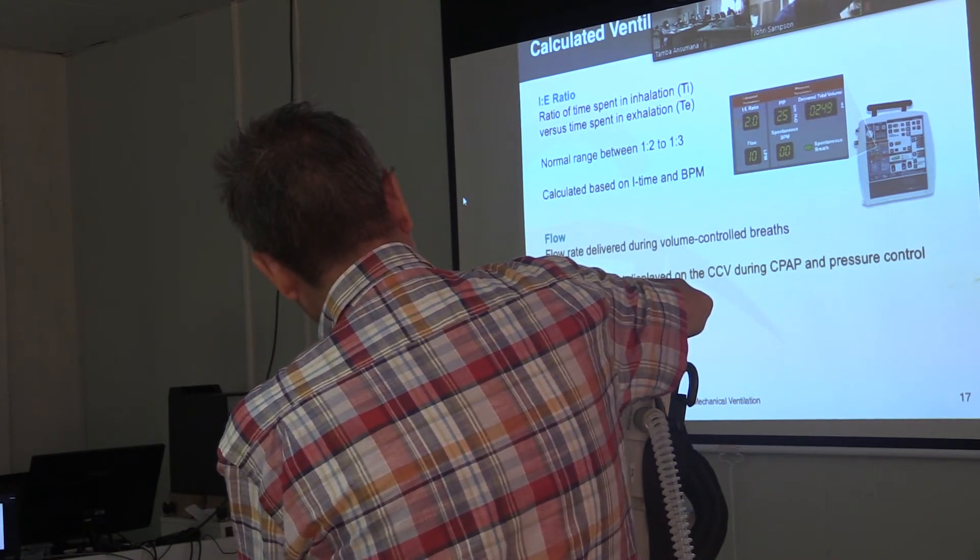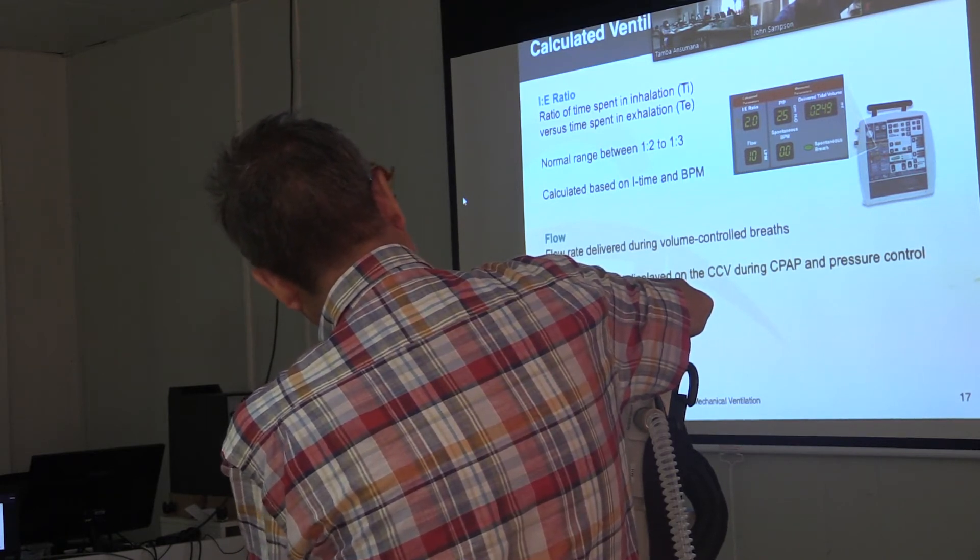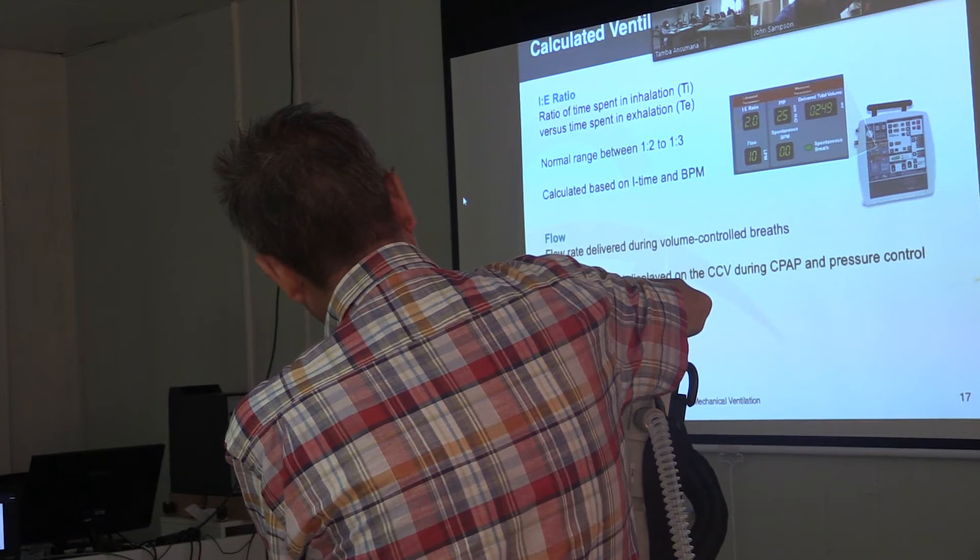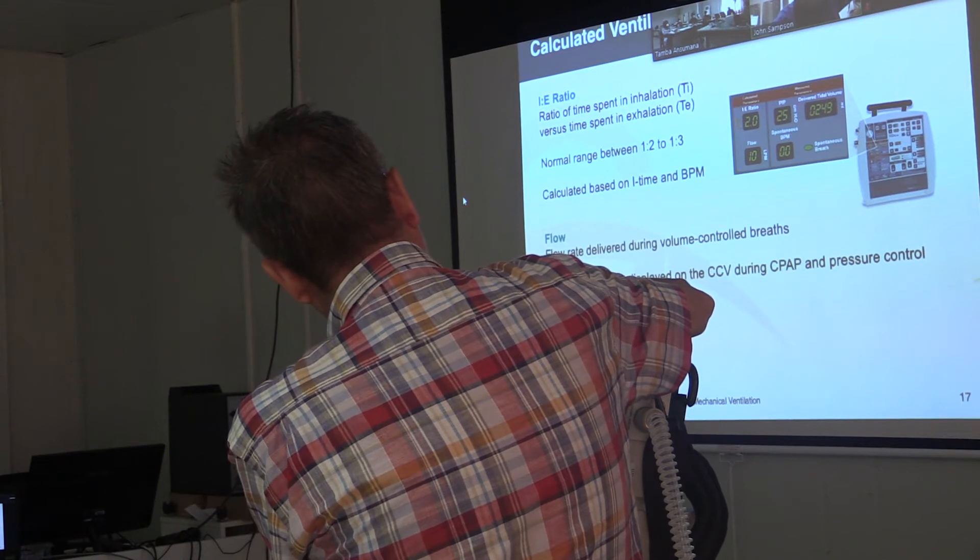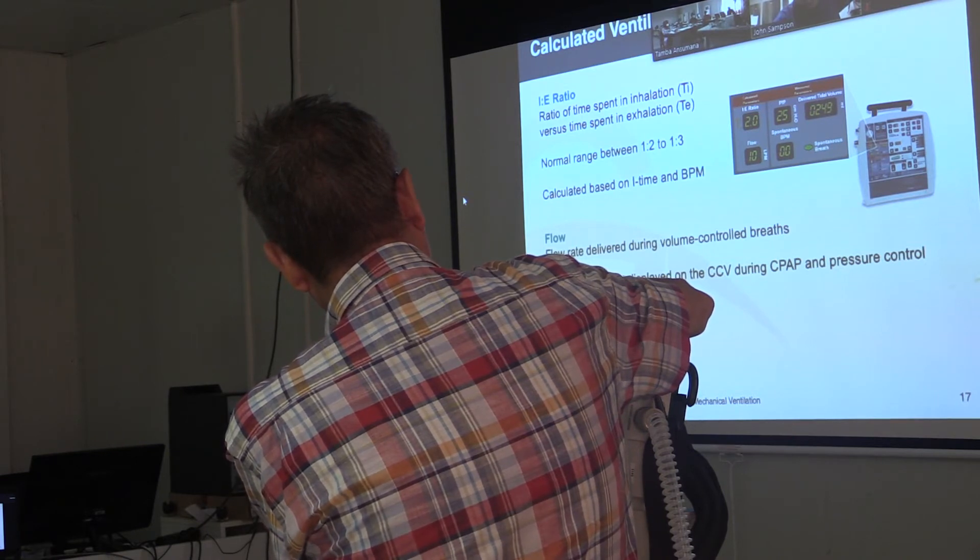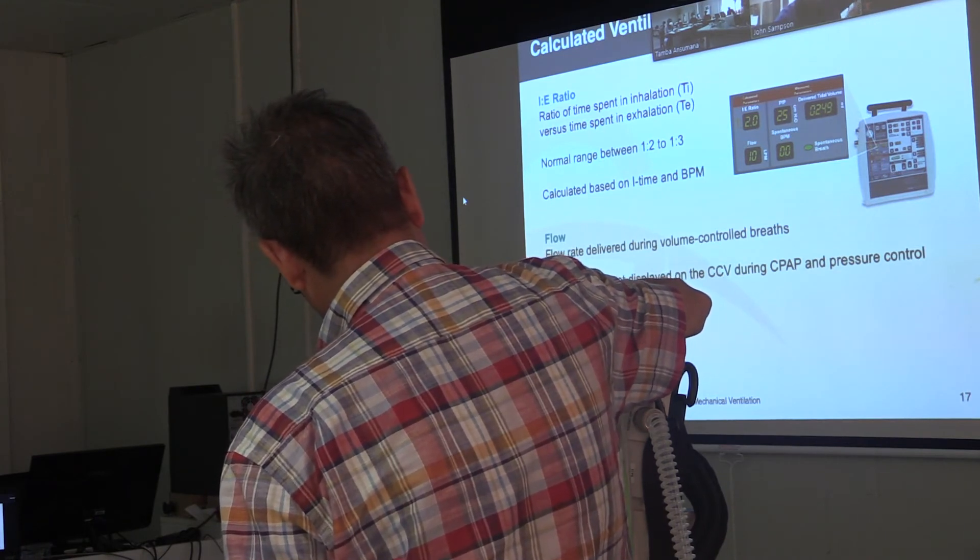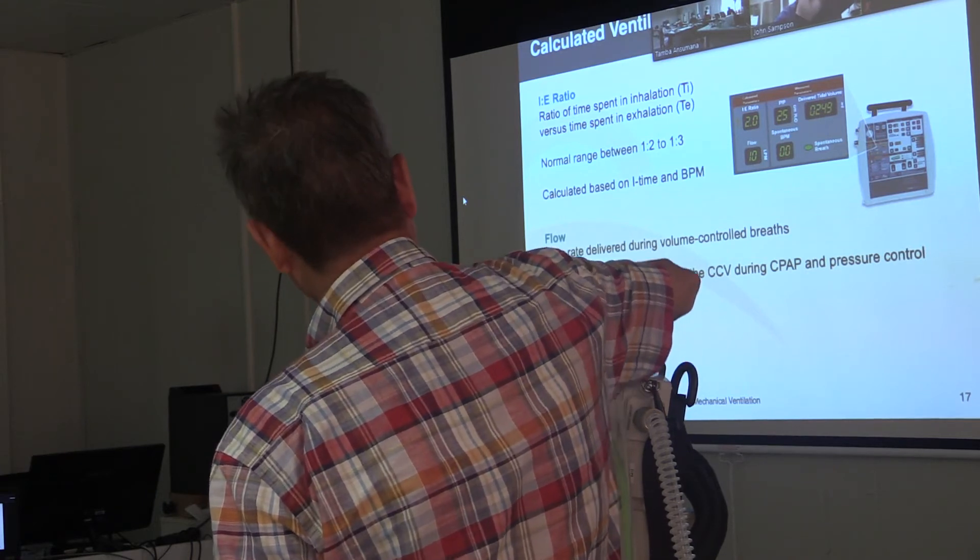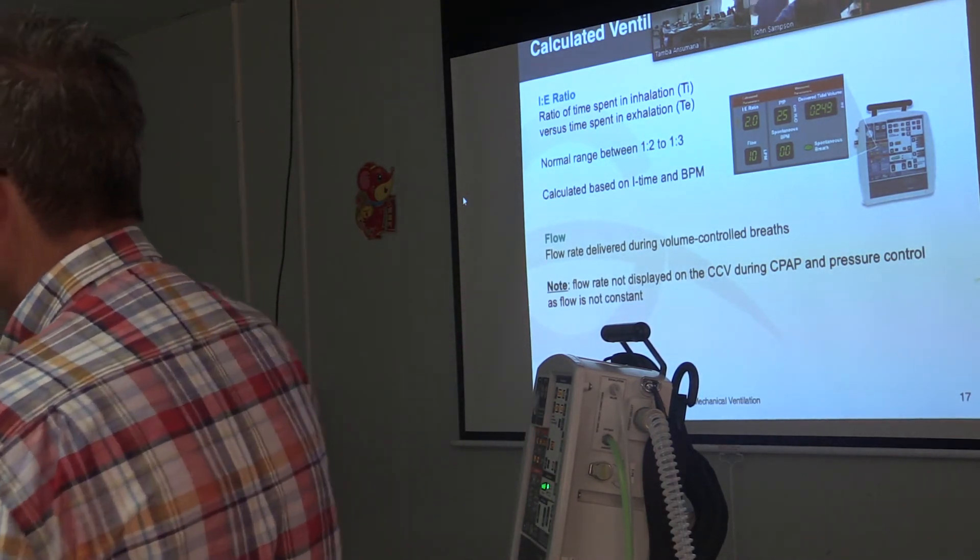It measures the spontaneous breaths per minute. Remember, you may set the breaths per minute for 10, but the patient might want to breathe 22. So that will show you the spontaneous breaths, and then it will light up every time they have a spontaneous breath. It's also showing you the flow, the liters per minute that's flowing through the ventilator. The flow can be very important, especially if you're using an oxygen concentrator or a flow meter to provide oxygen to this vent.